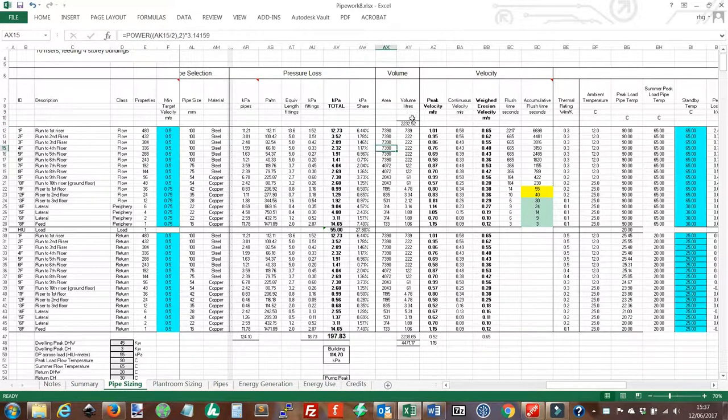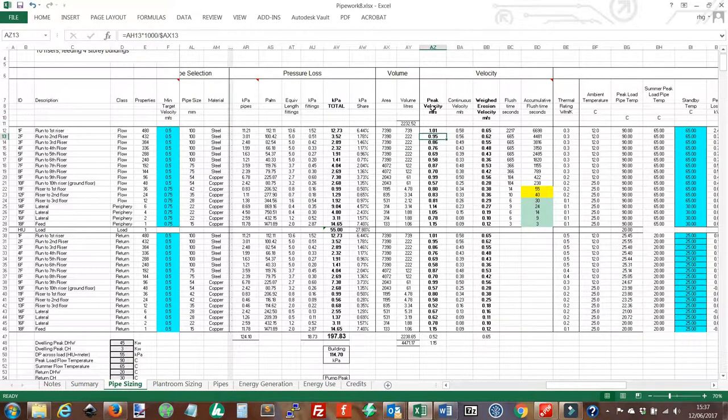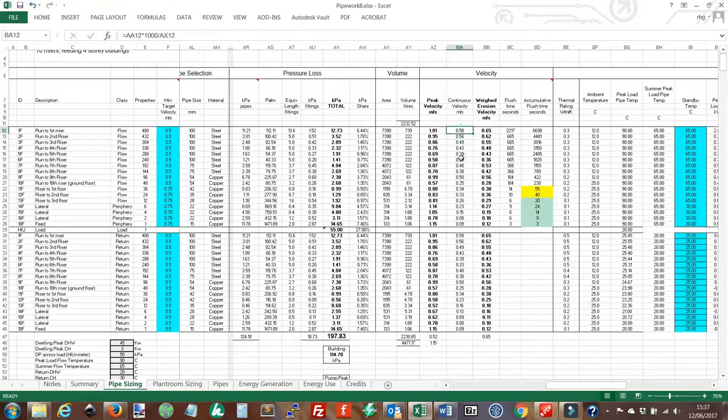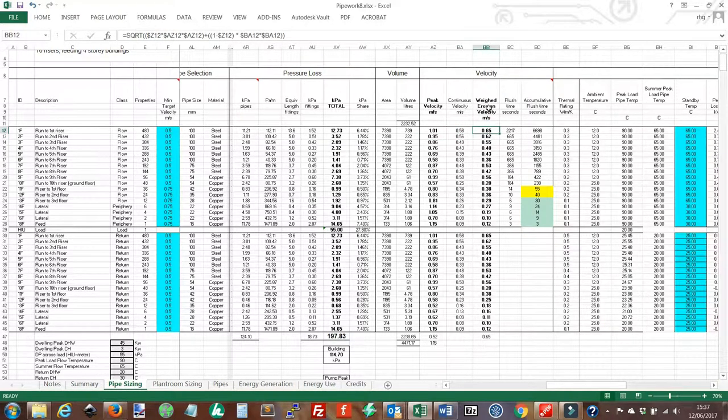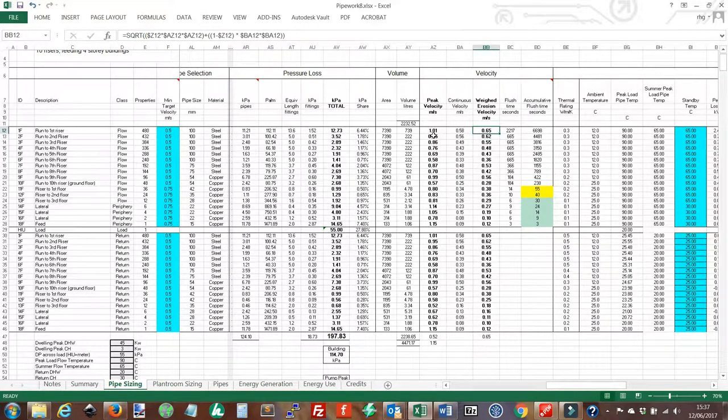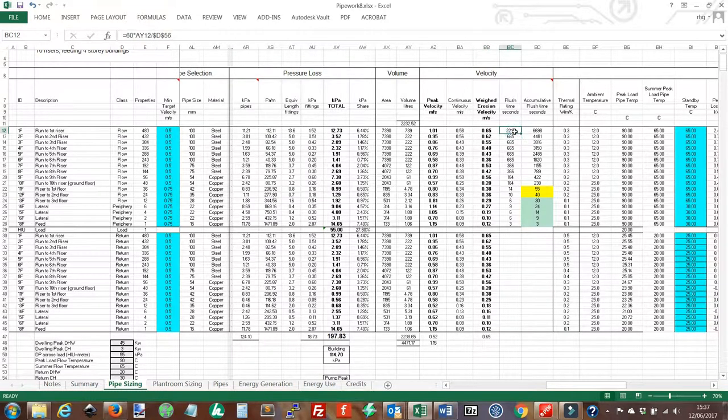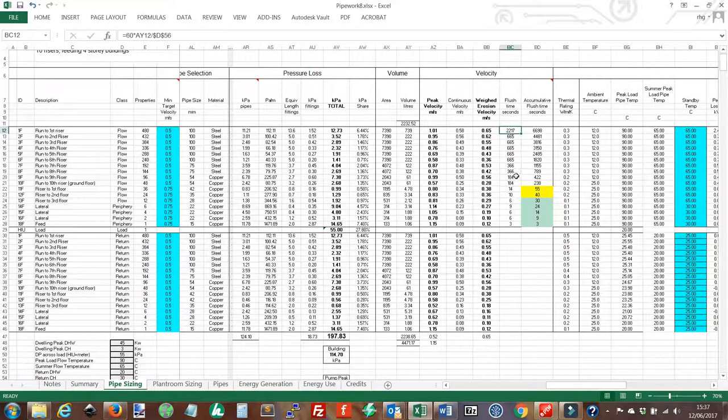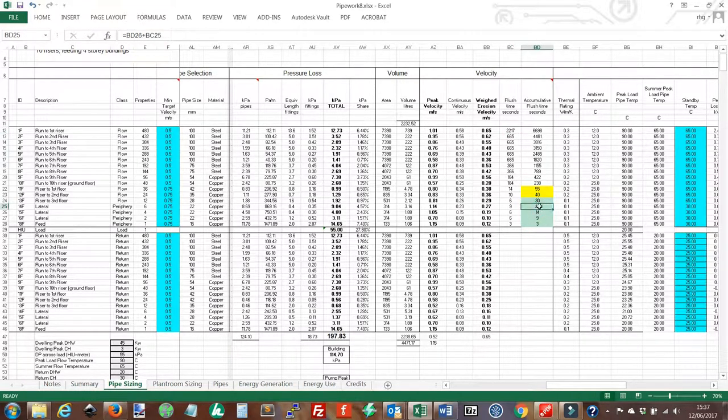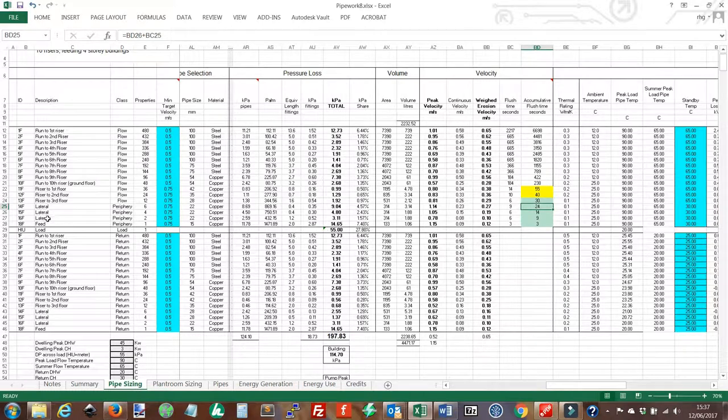We have the area of the pipe, the volume of the pipe. From that we can get the peak velocity, the continuous velocity, a time weighted erosion velocity. So this allows for the fact that the peak velocity only occurs for a small percentage of the time. We have a flush time. This is the time it takes to clear the pipe. And an accumulative flush time. So here it will take 24 seconds to clear our laterals and our feed to our property.